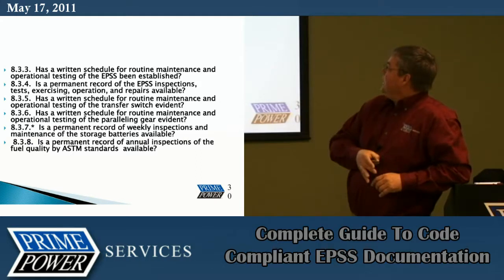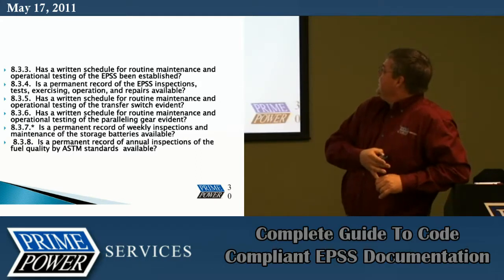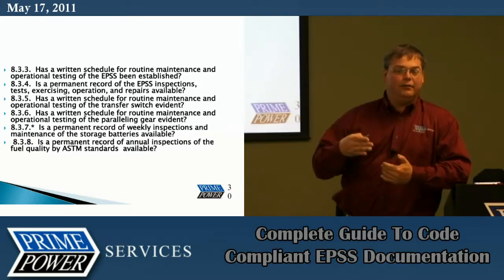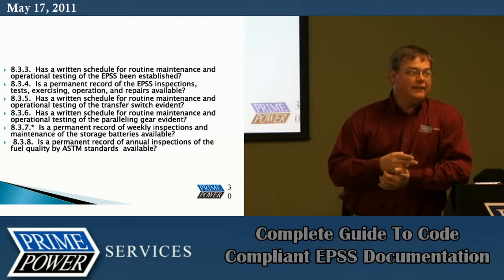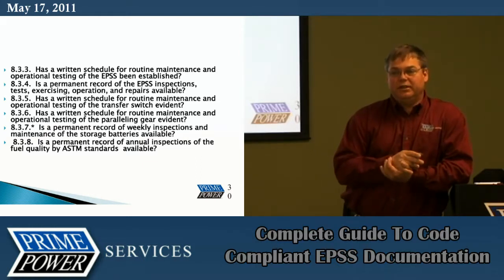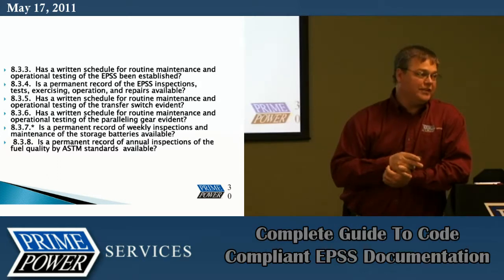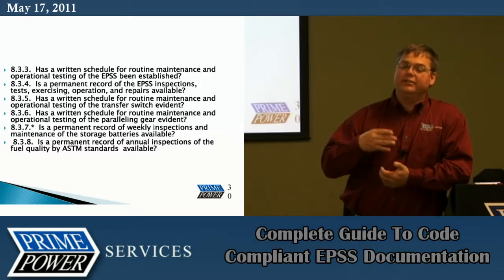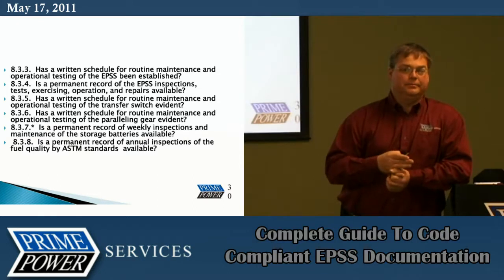Has a written schedule for routine maintenance, operation testing, and transfer switch been evident? Not only the generator, but you also have to do the same for the transfer switch. Transfer switches are a major component of your electrical distribution on the emergency power side. You have to maintain them to the same level as the generators.